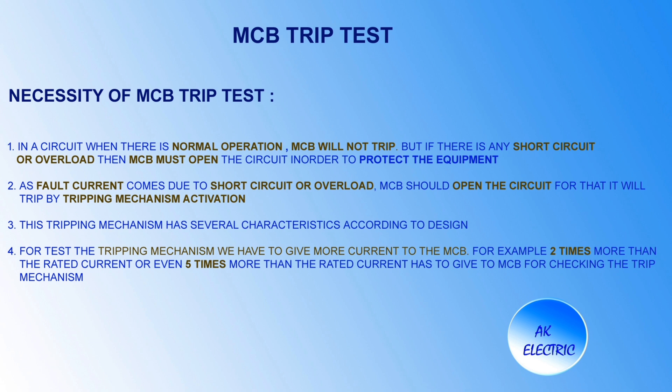This trip mechanism has several characteristics according to design. To test the trip mechanism we have to give more current to the MCB — for example, two times more than the rated current, or even five times more than the rated current has to be given to the MCB to check the trip mechanism.